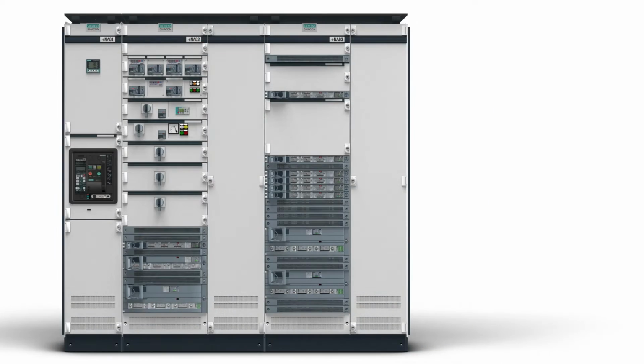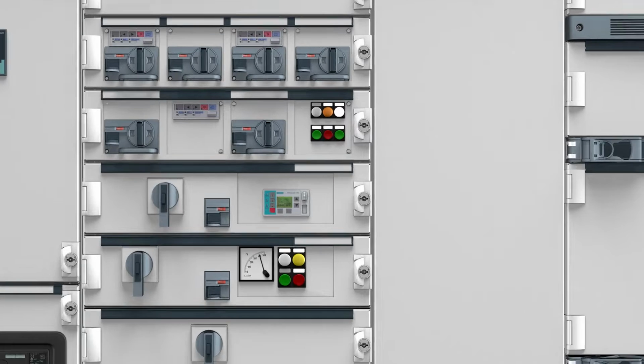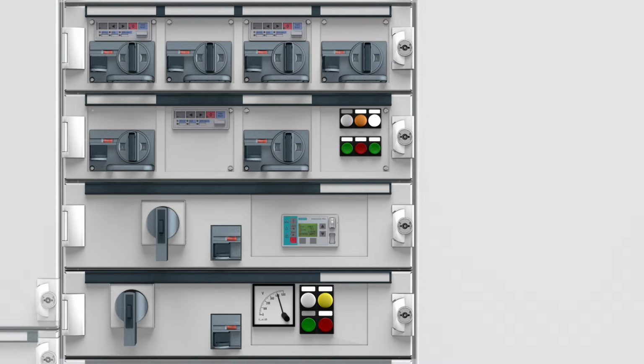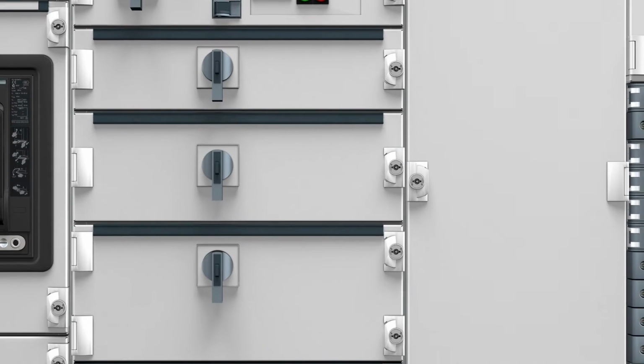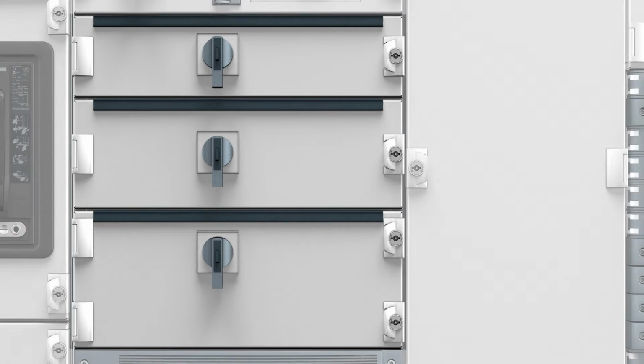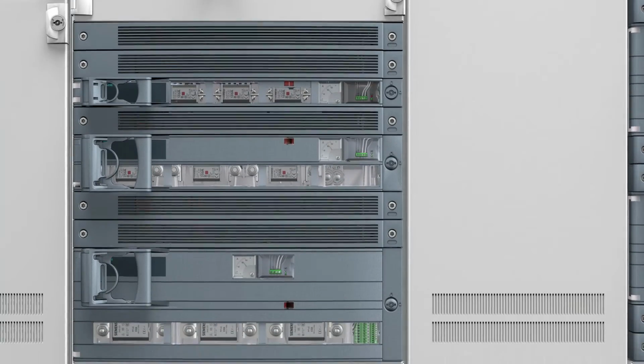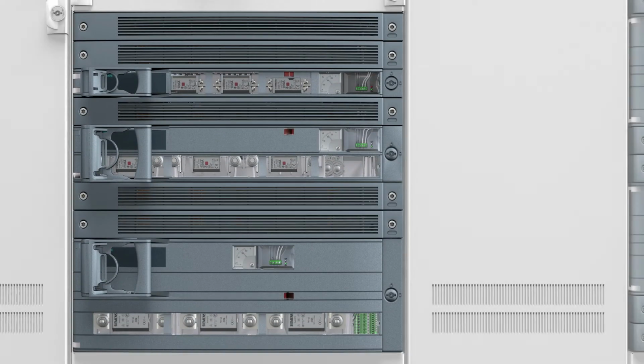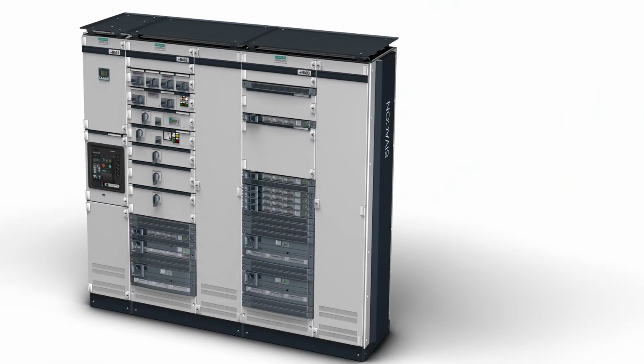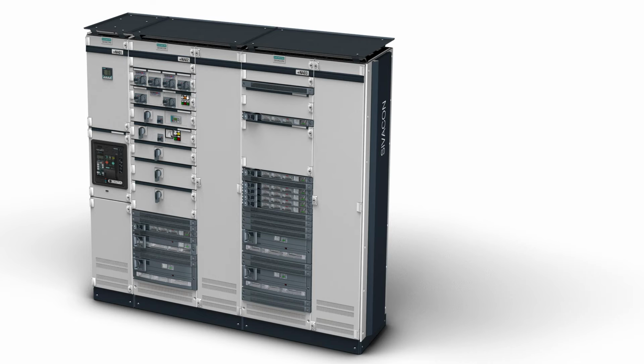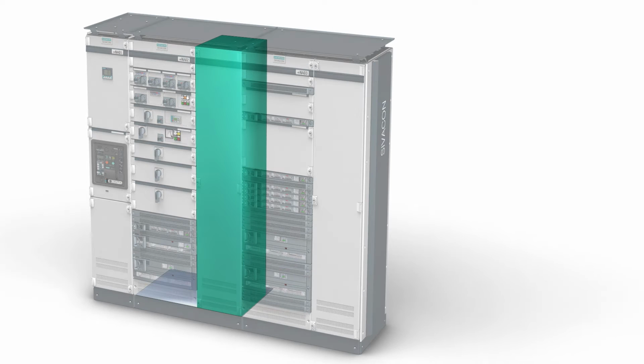The universal mounting design represents a combination of the withdrawable and fixed mounted design, as well as plug-in outgoing feeders in inline design. With frequently changing requirements, this design offers the necessary flexibility, as well as easy and safe handling. The cable connection compartment can be positioned laterally or at the rear.